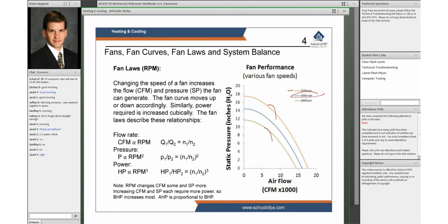But if we want to know where to look at about what speed we should be looking for, we can run this through the fan laws. So here is our first set of three fan laws related to the speed in RPM. Actually, it's speed in any measure since it's a ratio of speeds.